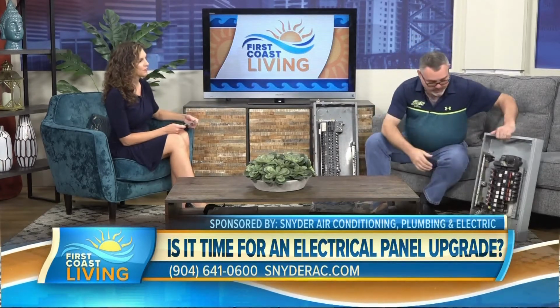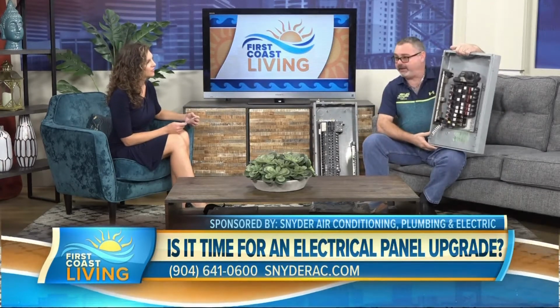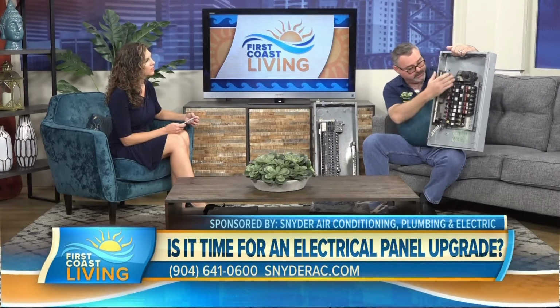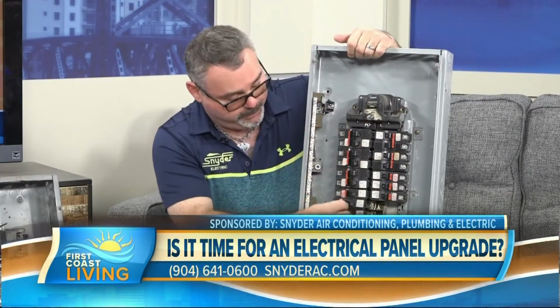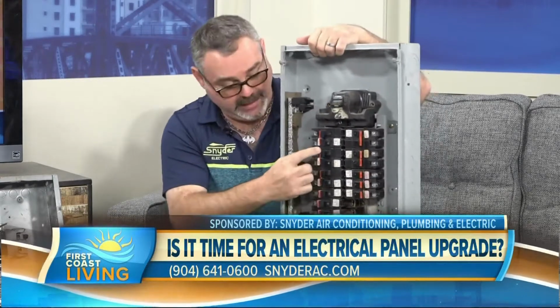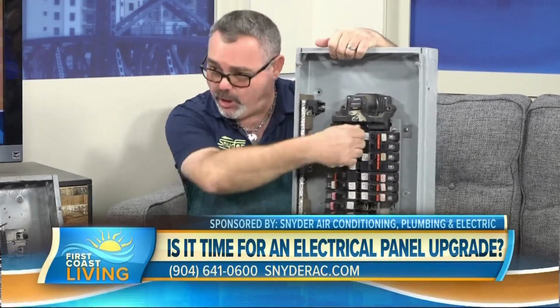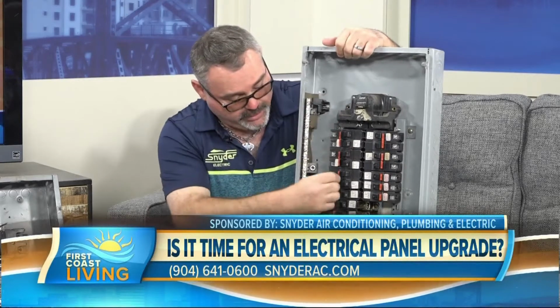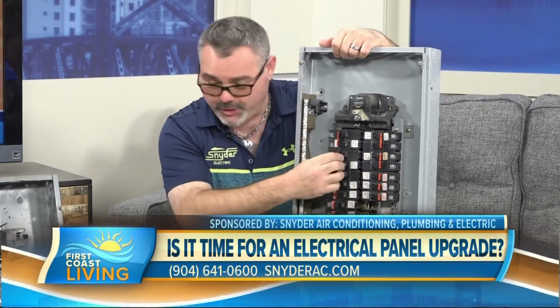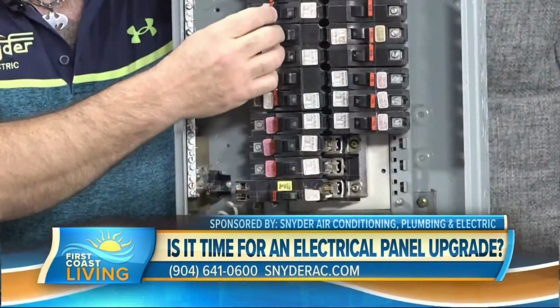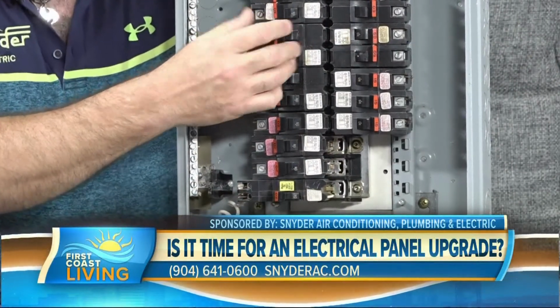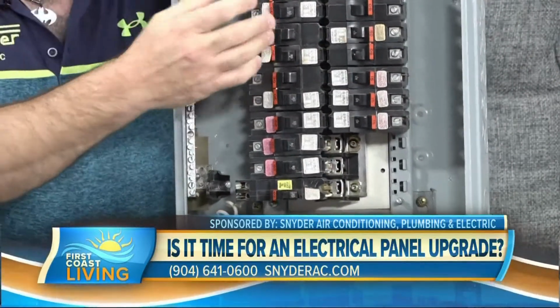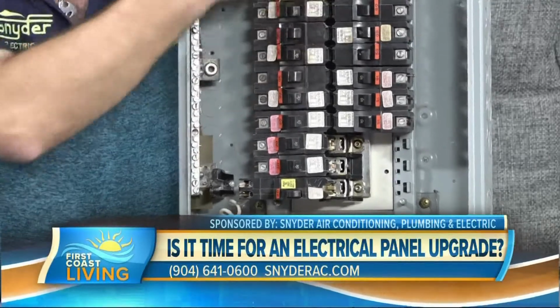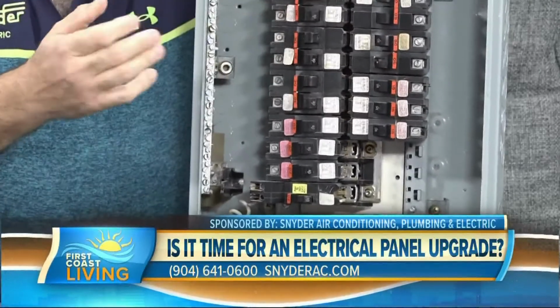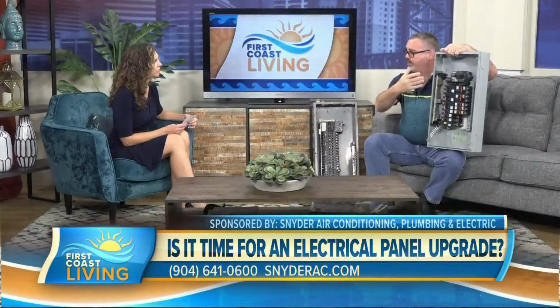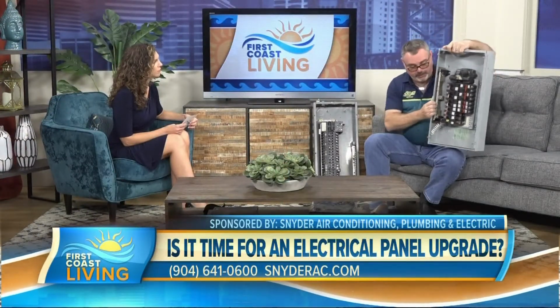I brought a couple of these right here. This is a Federal Pacific panel. We don't have the cover, but the breakers have red labels on them. That's what you'll find when you open your door, you'll see these numbers and the red labels. These are ones that have lost their UL listing. This is from about 20 years ago, so it's something that's been around a while. Again, the door will be on it, and you can open it and see the label saying Federal Pacific or FPE.